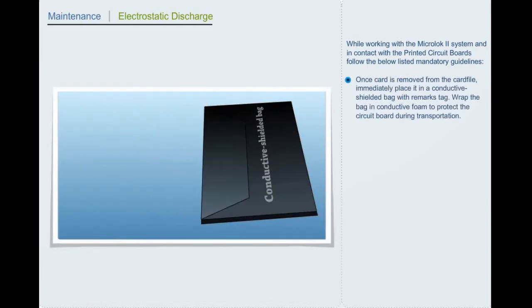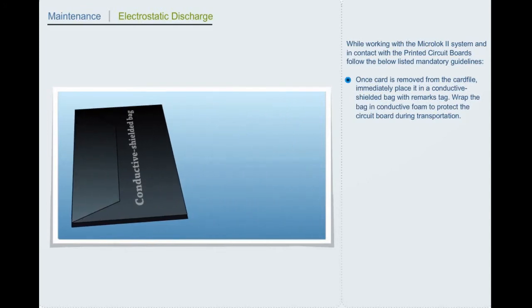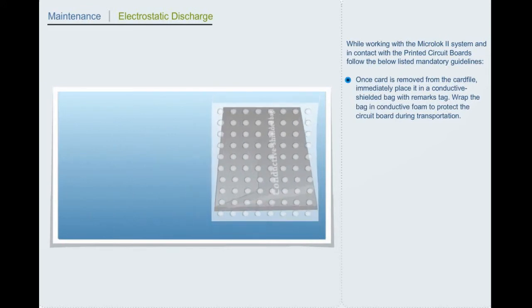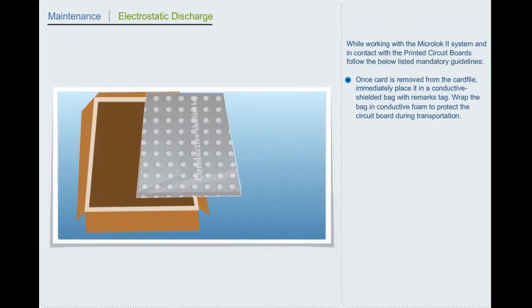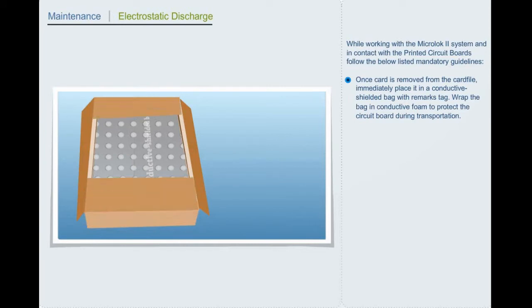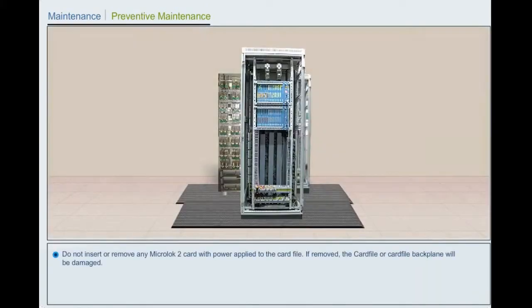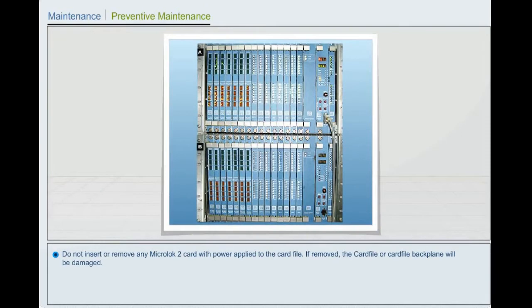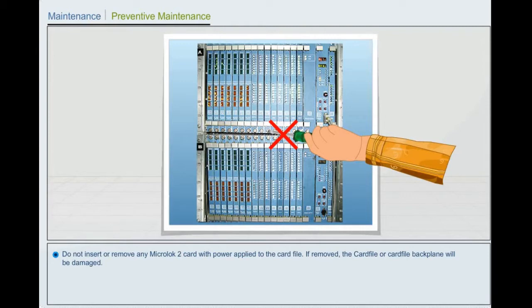Once a card is removed from the card file, immediately place it in a conductive, shielded bag with remarks tag. Wrap the bag in conductive foam to protect the circuit board during transportation. Maintenance. Preventive maintenance. Do not insert or remove any Microlok 2 card with power applied to the card file. If removed, the card file or card file backplane will be damaged.